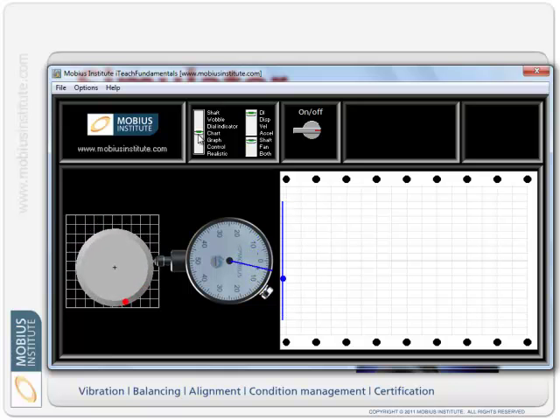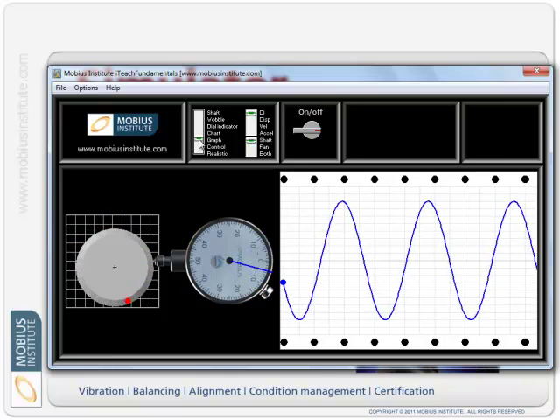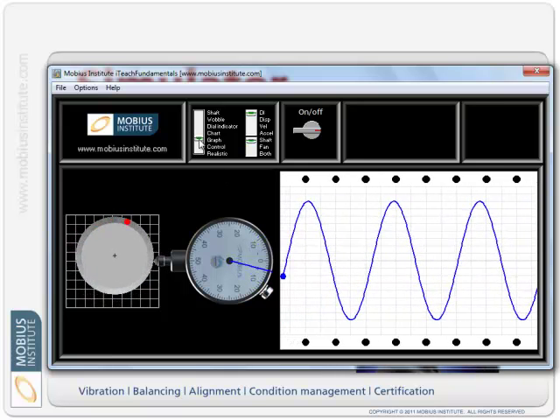What if we had a good old-fashioned chart recorder? They use these in lots of plants still today, but of course there are electronic measurement systems instead. When you look at those seismograph charts when there's an earthquake, this is the same sort of thing they're doing. What we've done now is we've taken the needle of the dial indicator and we've moved a blue pen up and down in sync with the needle swinging back and forward. And if we actually start the chart recorder, look what happens.